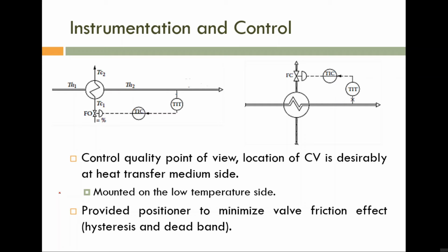Okay. Now the next question: the temperature of which side do we have to measure? The input side of the process medium or the output side? Yes, because we have to check whether the heat transfer is completed or not. So we have to check the output temperature of the process medium, which means we have to measure T2. Here you can see that in both cooler and heater, the output temperature of the process medium is measured.